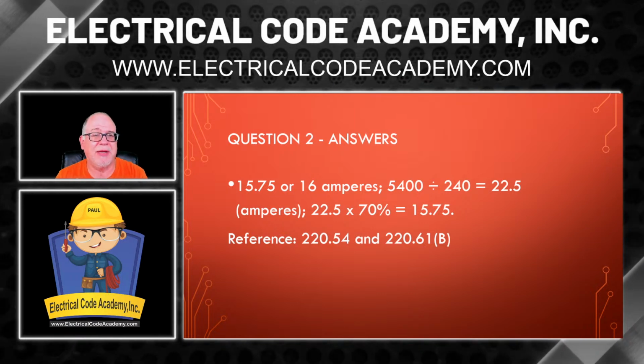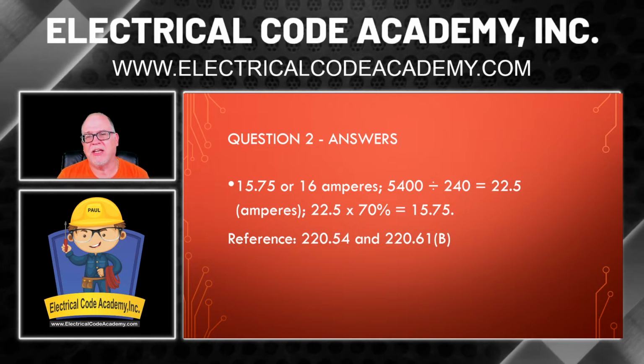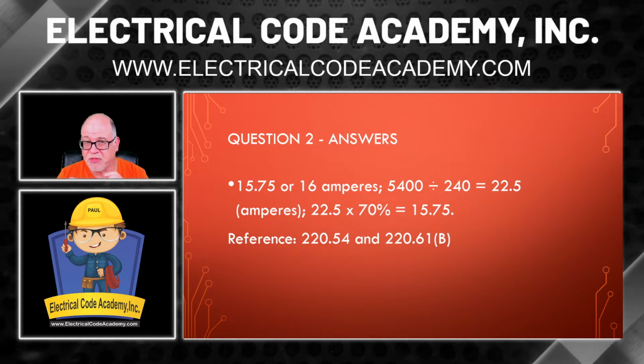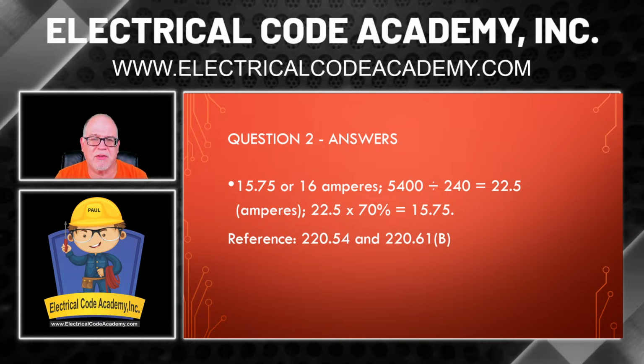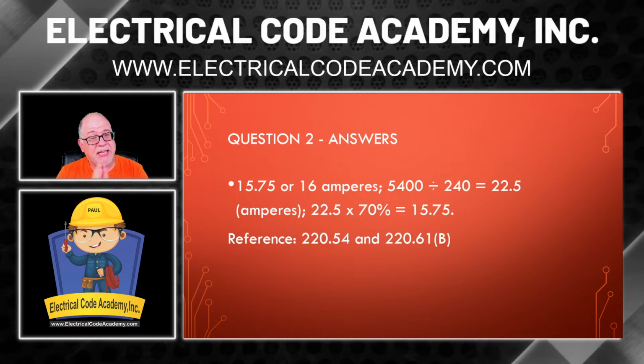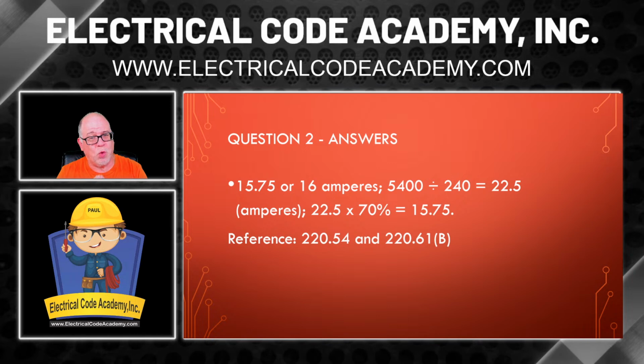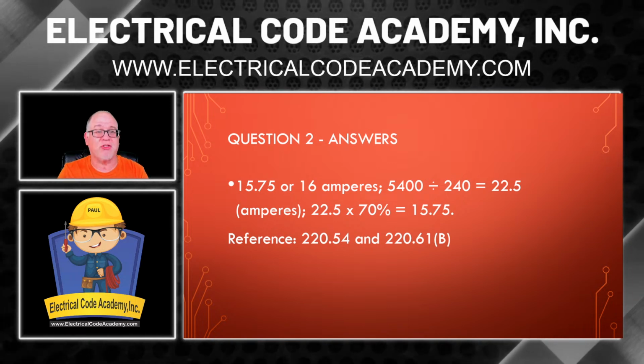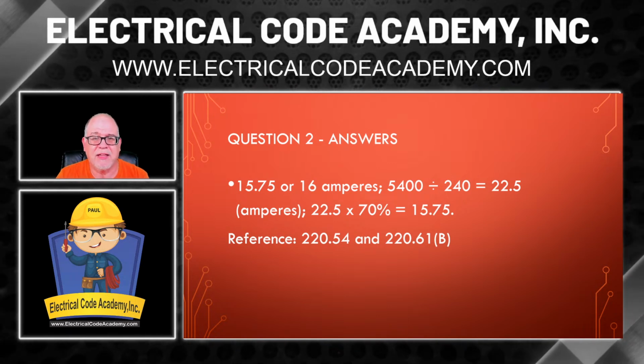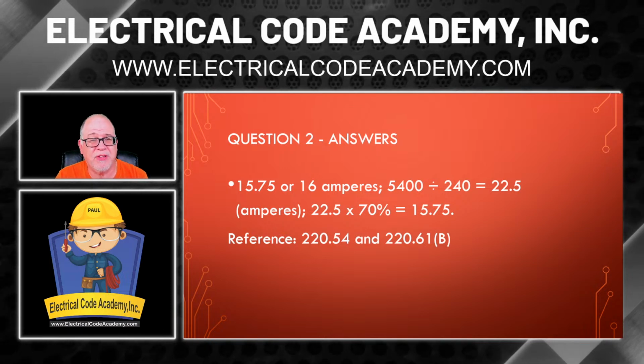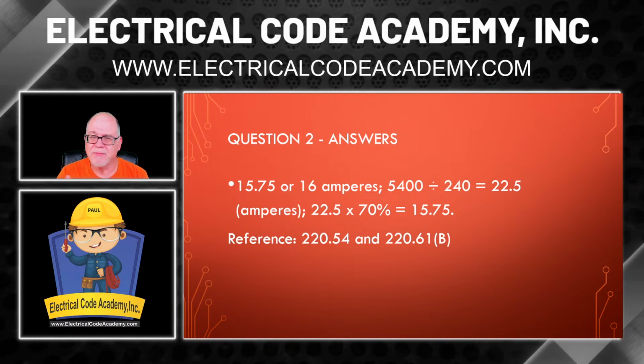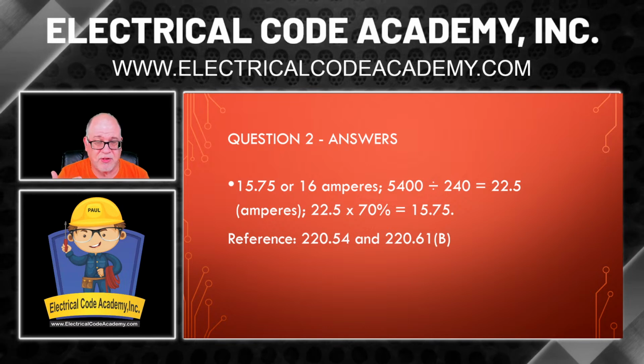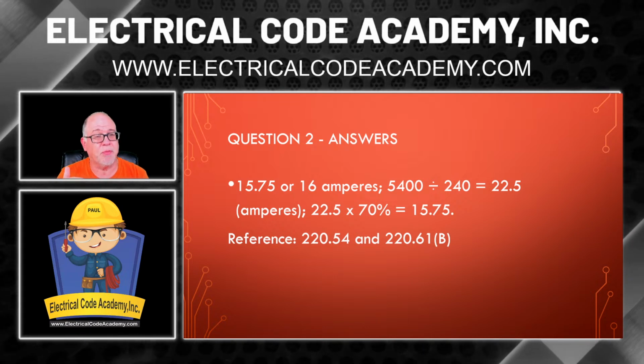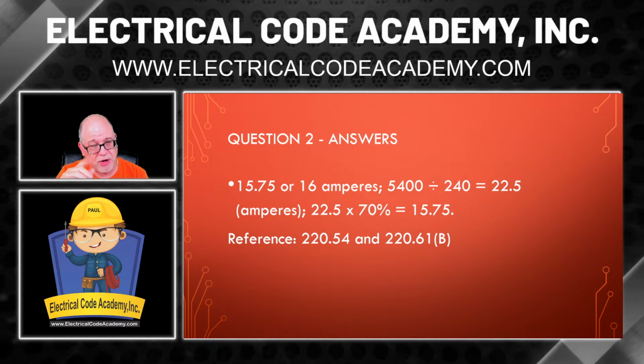Now, since we're dealing with amps, the code does allow you, if it's 0.5 or greater in amps, to round it up to the next available size and use that. But be careful, because if an exam question wants to know the actual contribution, then the more accurate answer would be 15.75. In the real world, 15.75 or rounding it to 16 is going to be fine. Right? You're permitted to round. Not required, you're permitted to round.